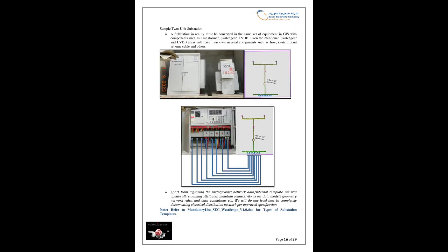Sample 2, unit substation. A substation in reality must be converted into the same set of equipment in GIS, with components such as transformer, switchgear, LVDB. Even the mentioned switchgear and LVDB areas will have their own internal components such as fuse, switch, plant, schema, cable, and others.